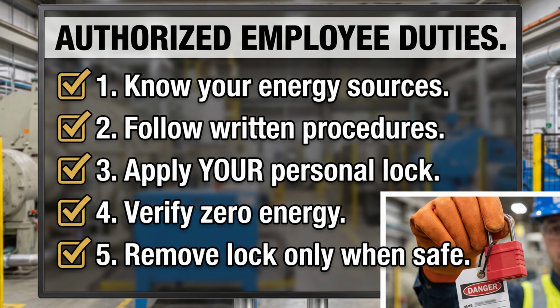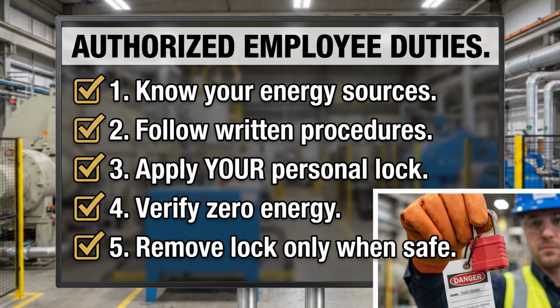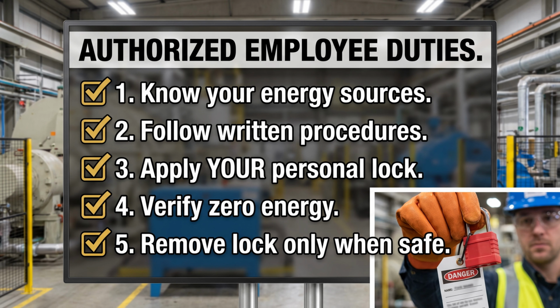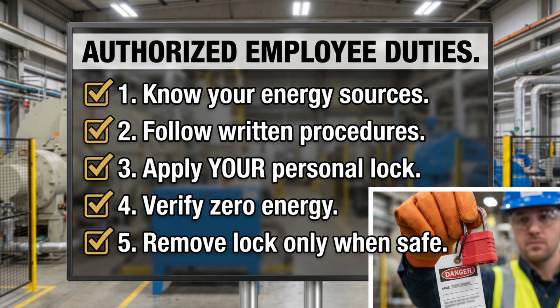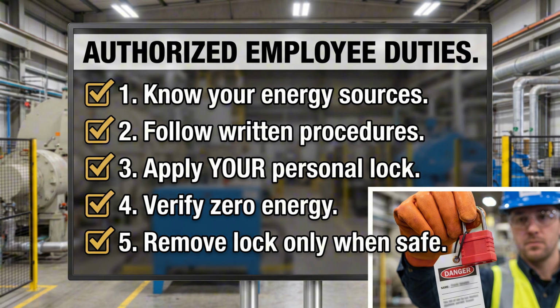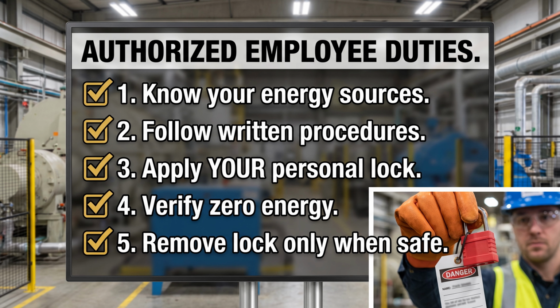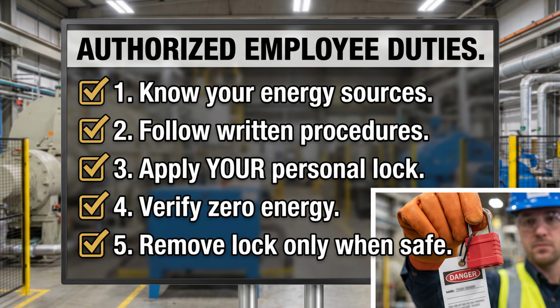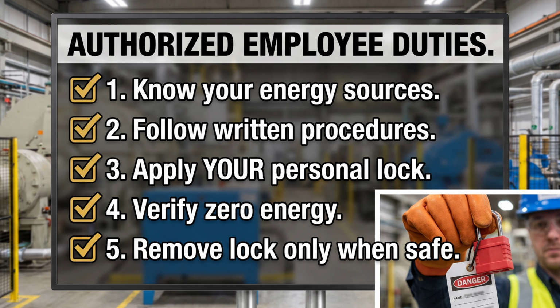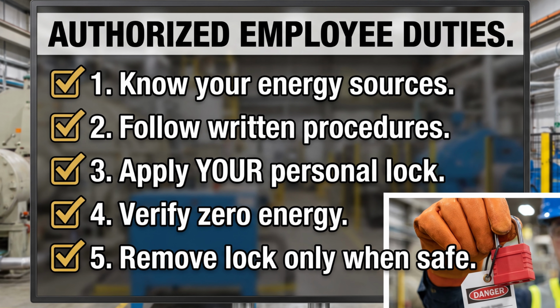As an authorized employee, your responsibilities are clear and non-negotiable. You must know the energy sources on every piece of equipment you service. You must follow your facility's written lockout procedures. You must apply your personal lock, no one else's. You must verify zero energy state before work begins. And you must remove your lock only when work is complete and the area is safe.